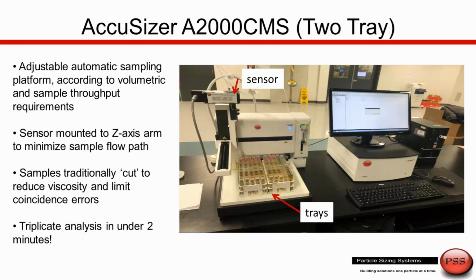It is not unusual at all to actually have these samples pre-diluted. And we may want to pre-dilute for two reasons. One reason is to assure the concentration is below the coincidence limit. The second reason we may dilute the sample is to reduce the viscosity to make sure that we can very efficiently aspirate the sample up through the sensor. So very often these are pre-diluted, and the sensor then will pass through all these samples in this tray.